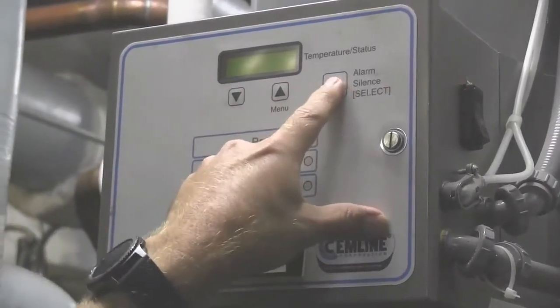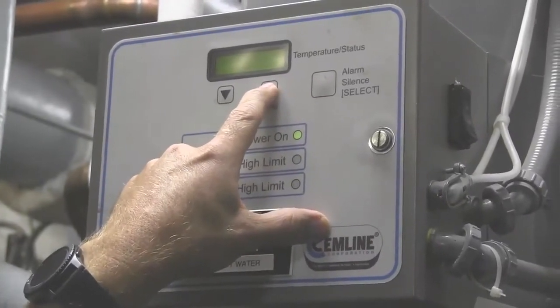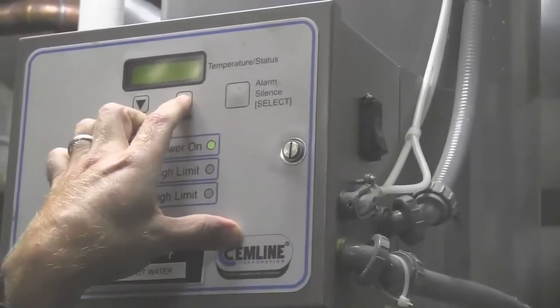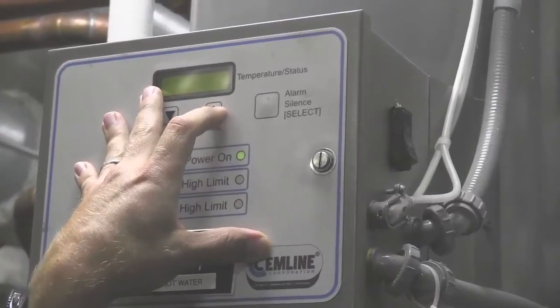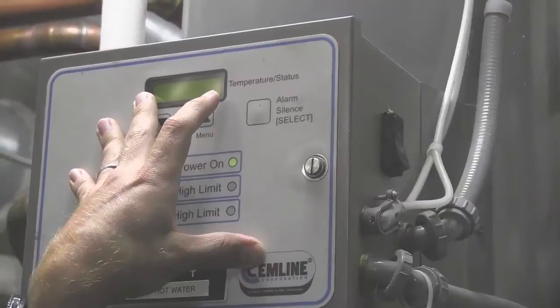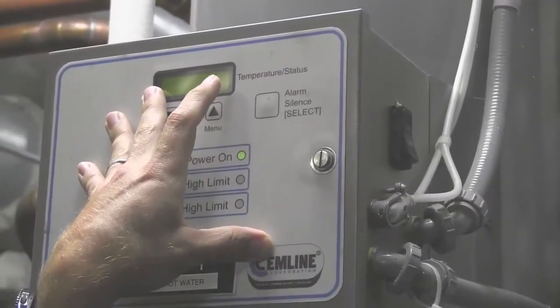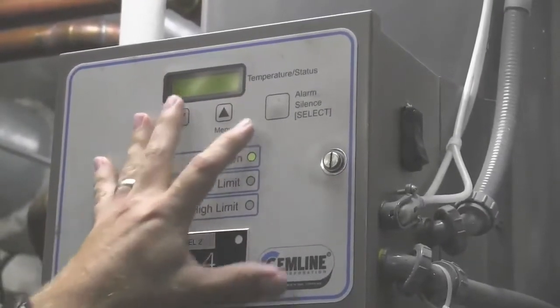So I'm just going to hit the enter button. So from the high limit number 1, what the high limit number 1 is, it's a sensor that's going to give you a visual and audio alarm only. It's not going to do anything else. It will periodically go into that high limit and it should adjust itself. It's just depending upon what's going on in the system, you may or may not see that. Going into high limit shouldn't be that big of a deal.